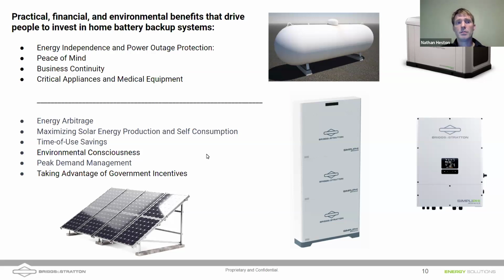Business continuity, again, that's where you're going to be able to just continue doing your business practices, have access to reliable power. The generators and inverters can do that for you. Critical appliances and medical equipment: there are plenty of customers, and we hear from them, that want to be able to keep important appliances or medical equipment online at all times. Now, generators and even most inverters are not approved for life-required medical equipment, right? Even though an inverter acts almost like a UPS, there are stringent requirements on UPS for medical devices. I will say, though, that this parallel breaks down here.